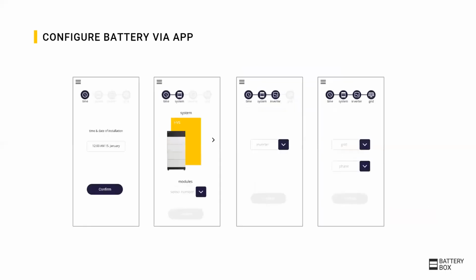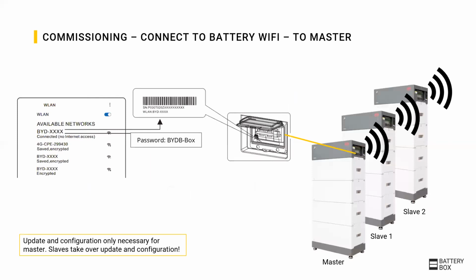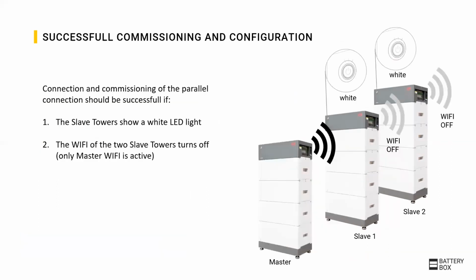The configuration then asks only for very few pieces of information: the current time, the inverter, the battery configuration, the type of use, and phases. If multiple batteries are in the system, you only need to update and configure the master battery. As shown here, you can identify the correct Wi-Fi of the master by the Wi-Fi name you can find at the system switch of the master BCU. You should be able to see if the configuration of the parallel system was successful when the LEDs of the slave towers turn white and the Wi-Fi of the slave towers disappear.